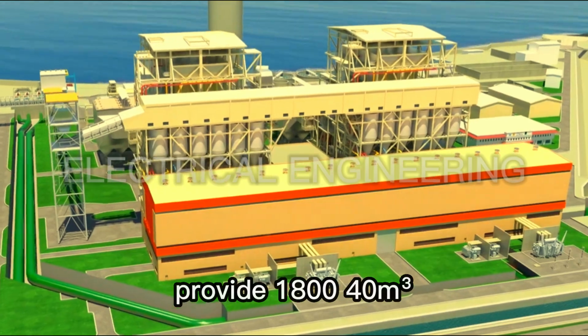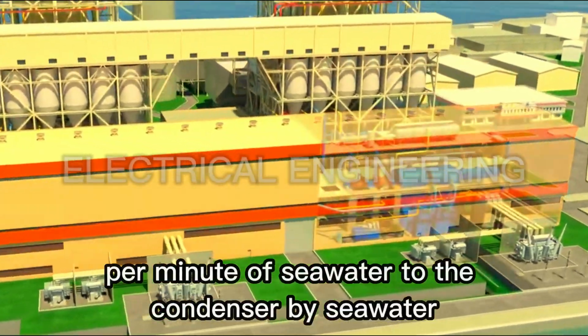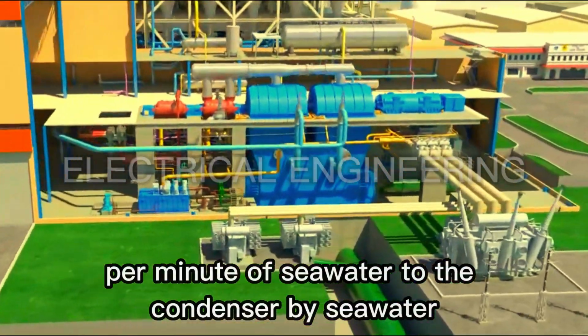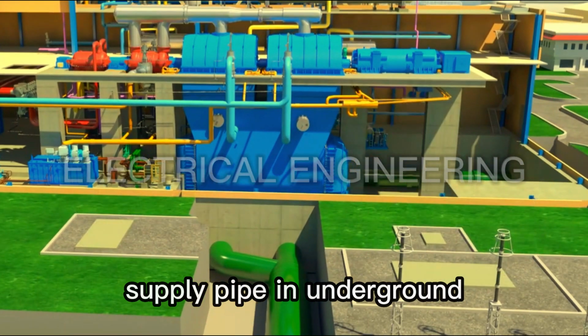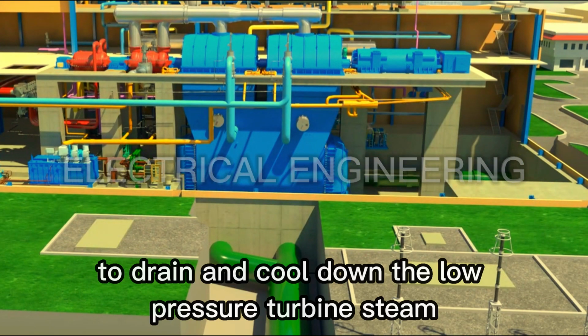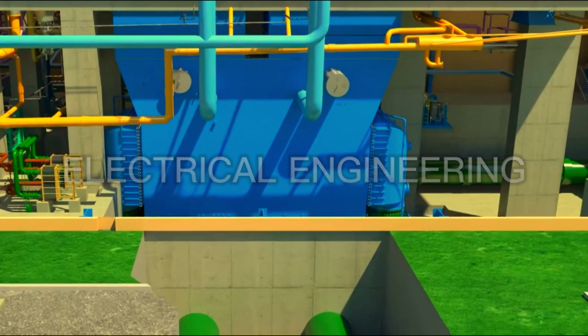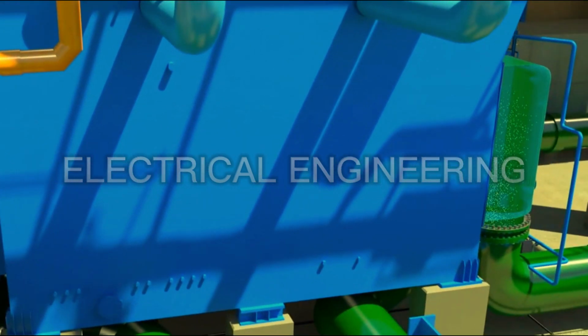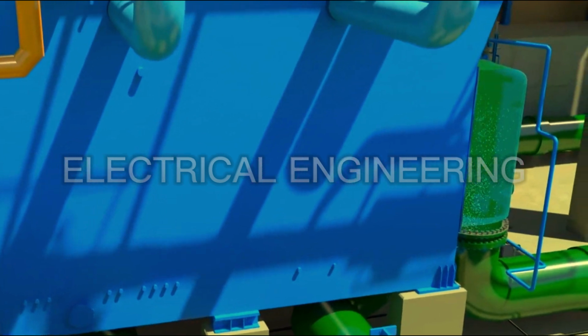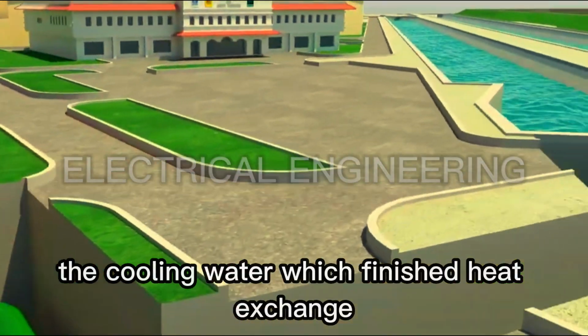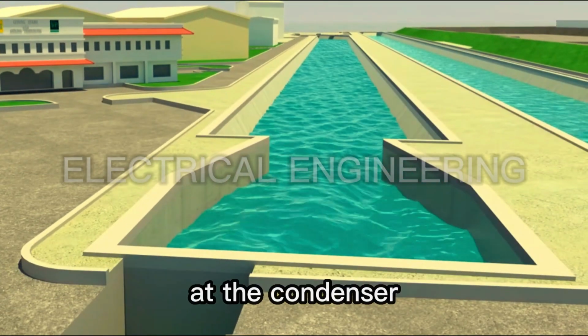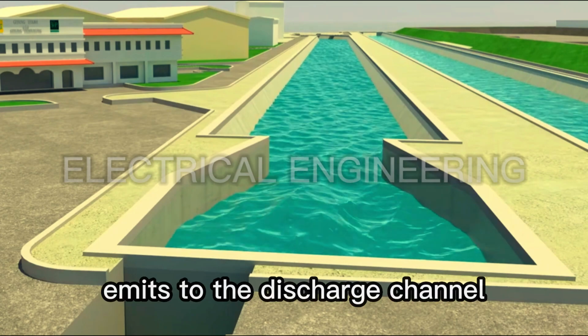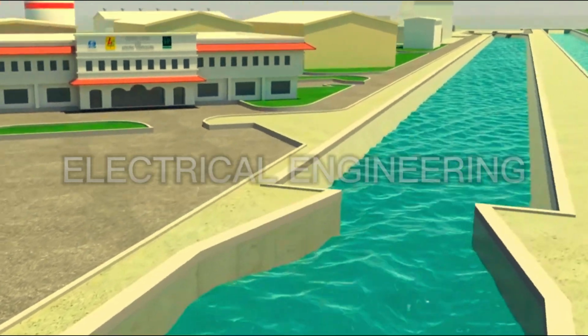Provide 1,840 cubic meters per minute of seawater to the condenser by the seawater supply pipe and underground to drain and cool down the low-pressure turbine steam. The cooling water which finished heat exchange at the condenser emits to the discharge channel along the discharge tunnel.